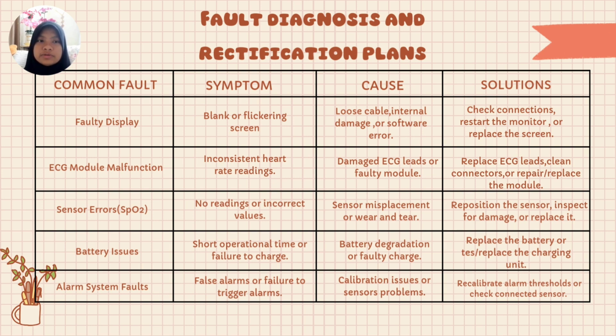After that, the common fault is battery issue. The symptom is short operational time or failure to charge. It is caused by battery degradation or faulty charger. The solution is to replace the battery or test or replace the charging unit.